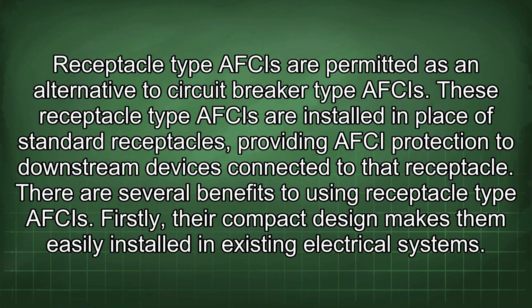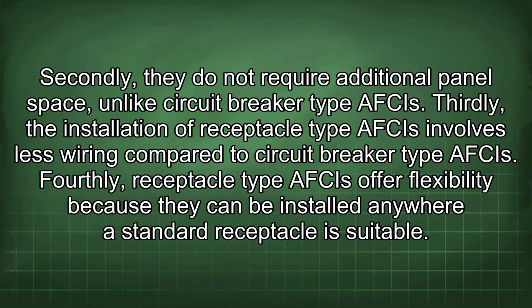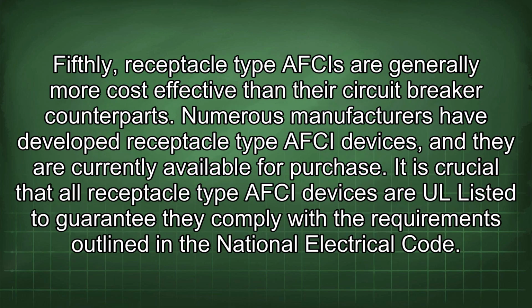There are several benefits to using receptacle type AFCIs. Firstly, their compact design makes them easily installed in existing electrical systems. Secondly, they do not require additional panel space, unlike circuit breaker type AFCIs. Thirdly, the installation of receptacle type AFCIs involves less wiring compared to circuit breaker type AFCIs. Fourthly, receptacle type AFCIs offer flexibility because they can be installed anywhere a standard receptacle is suitable. Fifthly, receptacle type AFCIs are generally more cost-effective than their circuit breaker counterparts.